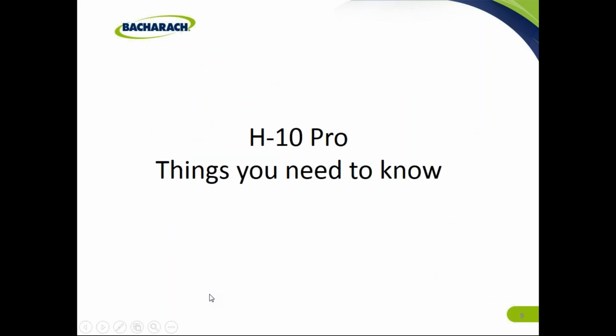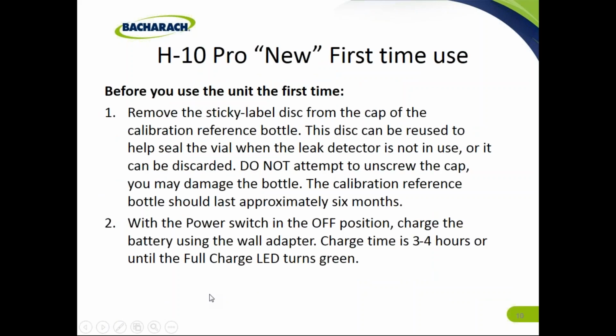The H10 Pro, things you need to know. Before you use the unit for the first time, remove the sticky label disc from the cap of the calibration reference bottle. This disc can be reused to help seal the vial when the leak detector is not in use, or it can be discarded. Do not attempt to unscrew the cap. You may damage the bottle. The calibration reference bottle should last approximately 6 months.